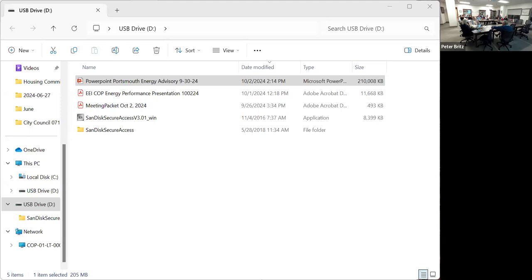Before we leave this building, just so everyone is aware, the 2-pipe system we have—you've all heard of the mold situations we've had in this building and the condensation. The 2 pipes happen to be black iron pipe, wrapped with pipe insulation. There are a lot of vertical pipes that go up chases, and when we have 52-degree cold water traveling through that pipe within a warm cavity, you can imagine the condensation forms very quickly.